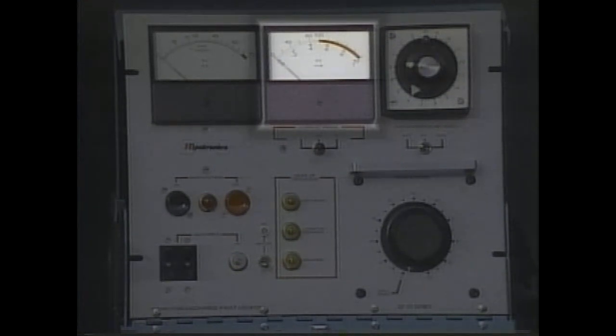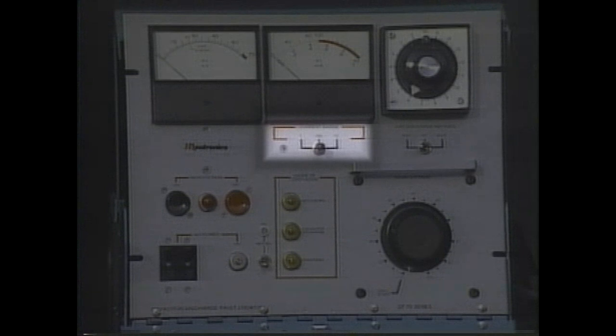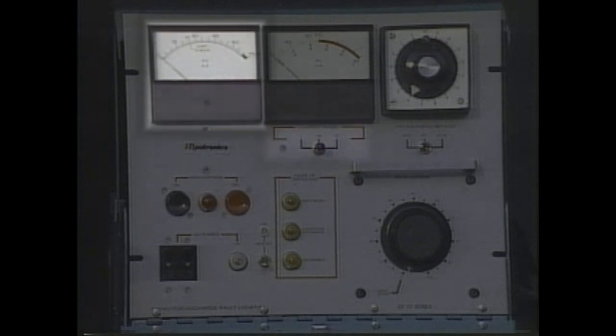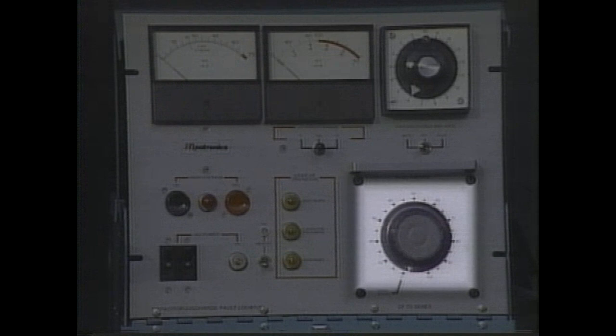This meter has a 3-scale range, depending on where the little 3-position switch is set. The range switch is just below the current meter. It allows the operator to control the amount of current used on a burn. The top left meter is the high voltage meter that tells how much voltage is being stored in the capacitor for a thump.